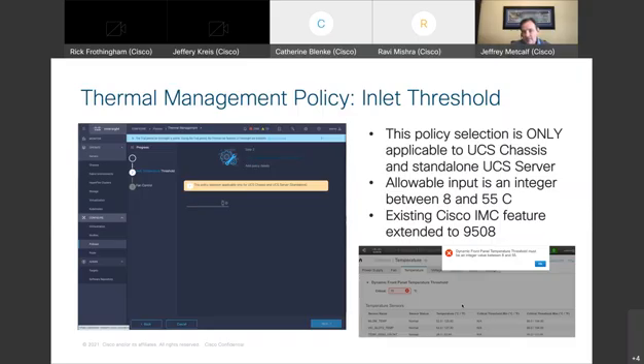Okay. So what I want to talk about here is the policies. This is a snapshot of Intersight and some of the things that we've done on the thermal side. If you're familiar with the C-Series today in standalone mode, there's a feature called dynamic inlet temperature threshold. The C-Series can support those classes that I talked about earlier, ASHRAE A2, A3, and A4. They have different upper limits. So we allow the user to go in and select the upper limit for that threshold. This is being extended to Intersight and will apply to the 9508 program as well. So it'll be a policy that's applied to a server or a chassis, right? So it's agnostic whether it's a server or a chassis. And if you're familiar with UCSM threshold policy, it's very similar to that, a user-defined threshold. Okay, next slide, please.